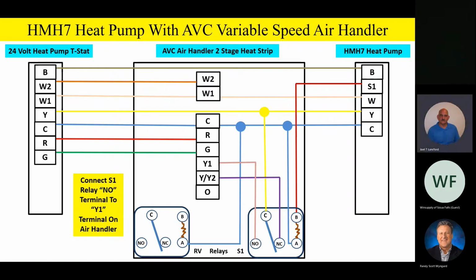Now on the RV relay, we're going to take the other side of the relay coil. One side of the relay coil goes to 24-volt common. You'd expect that. The other side of the relay coil is going to go up and tie onto the B terminal for reversing valve operation outside. Now, this is how this works.